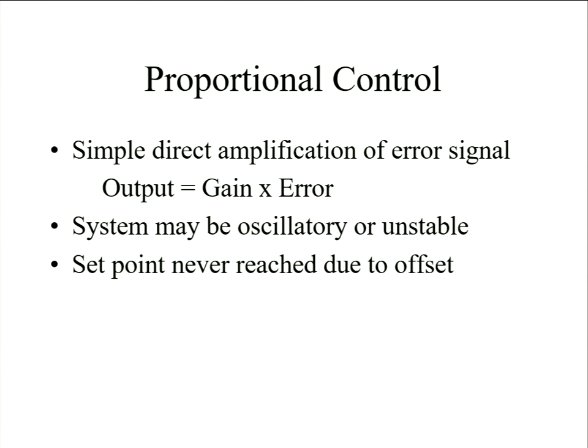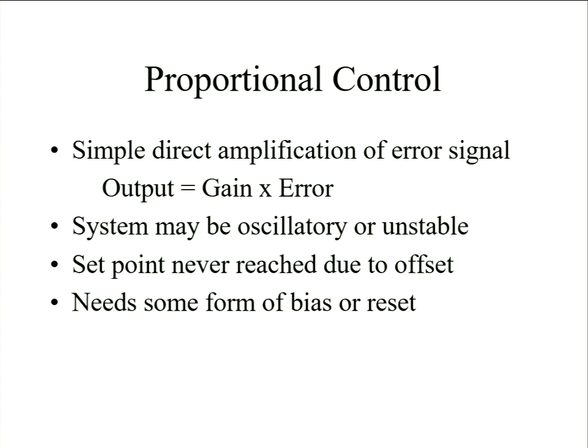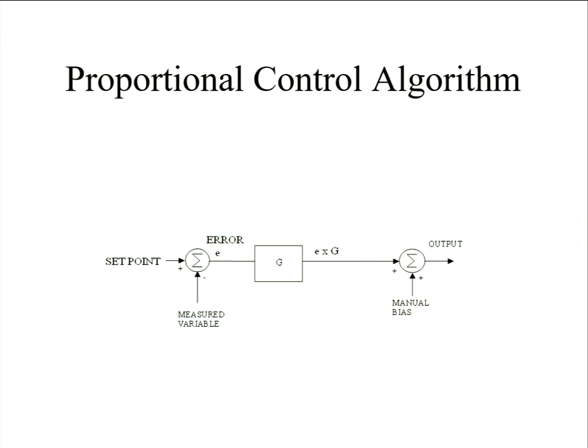So what the controller is doing here, we've got our set point, measured variable, and error, multiply it by that, and then you now have a bias or an offset. So if you know what the output wants to be at a particular place, if you needed 50% of output with zero error, you can add that on. But as soon as you move away from that basis on what you've set, that manual bias, again you'll have some error. You won't quite have the measured variable equal to the set point.